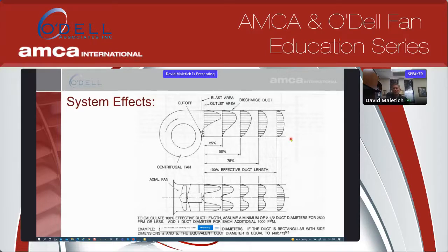What's 100% of your effective duct length? It's 2.5 duct diameters for the first 2,500 feet of velocity, and an additional duct diameter for each 1,000 feet of velocity after that. So if you have 6,000 feet of velocity, you should have 6 duct diameters. If you have 1,000 feet of velocity, you still need to have that minimum 2.5 duct diameters. That is to get full regain. However, if you look at this chart here, or this picture, at 50% of your effective duct length, you're getting about 80% of your regain there. And that's a pretty significant amount.